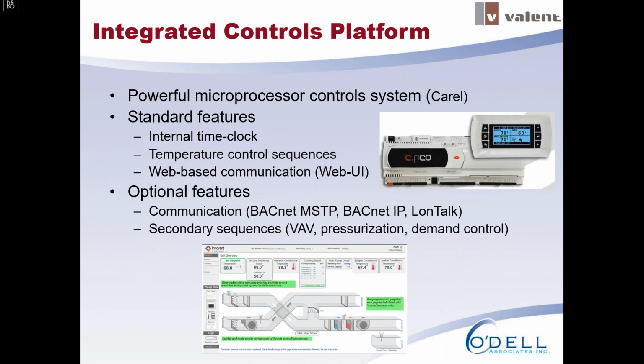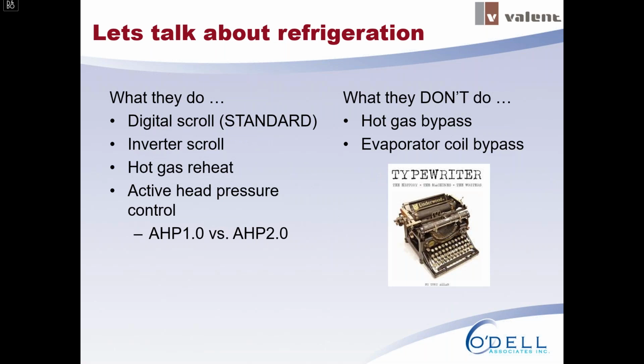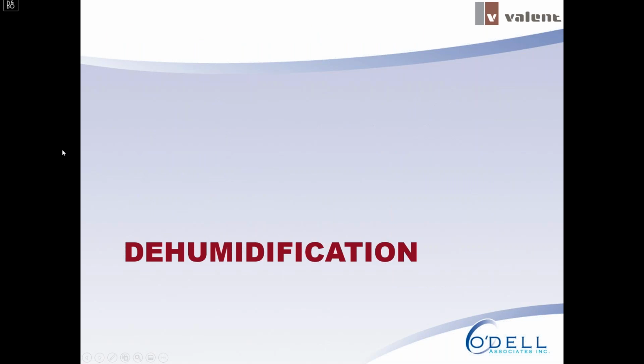So next I want to talk about where I really want to dig in, because on the heating side of things it's pretty straightforward: gas heat, gas heat, electric heat. So what I wanted to really dig into here, and maybe get Brian to help us a bit more with the details, is specifically refrigeration. What Valent really does, and does well, in their refrigeration cycles is digital scrolls. They also have inverter scrolls, hot gas reheat, and some active head pressure controls, which we'll discuss a little further. What they don't do within the Valent offering is hot gas bypass for capacity control, nor do they do evaporator coil bypass for dehumidification control. We can talk about those things a little more if people have questions about why, but Brian's going to really dig into what they do well. So Brian, from here, I'll let you take it away.